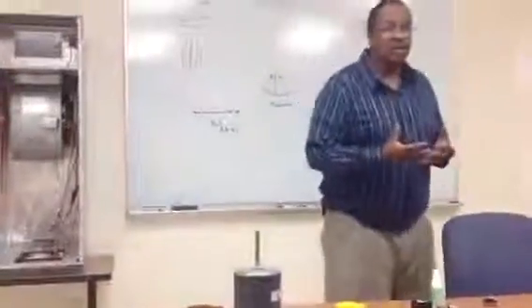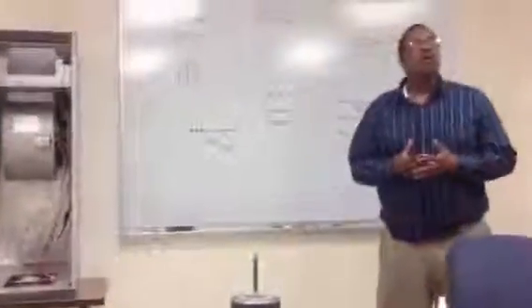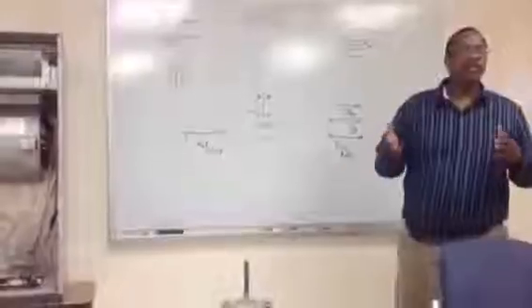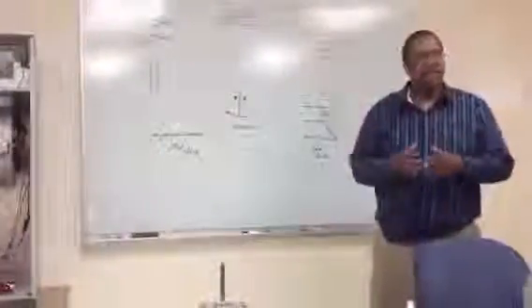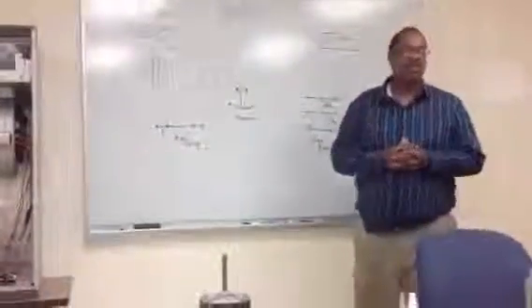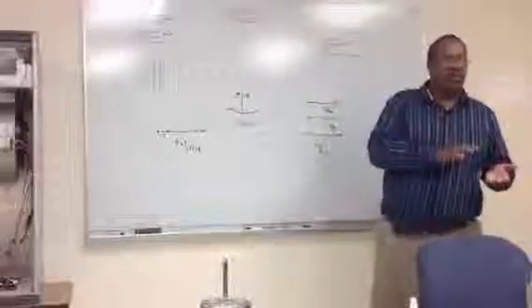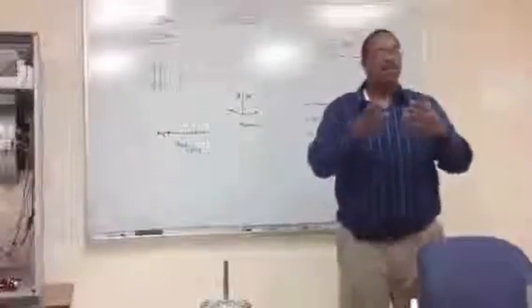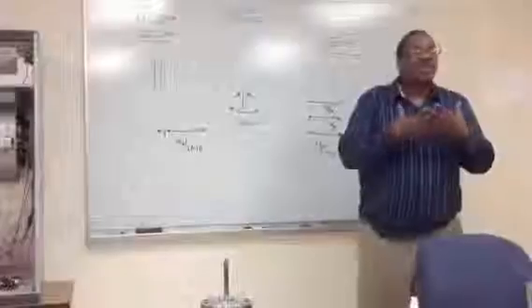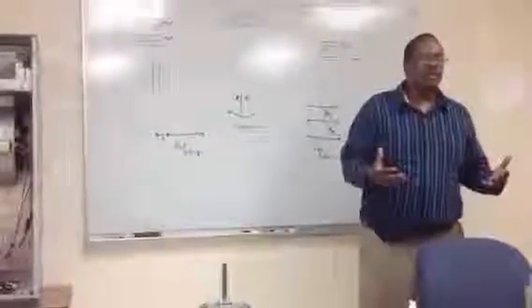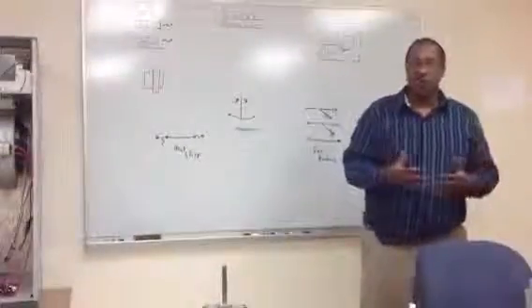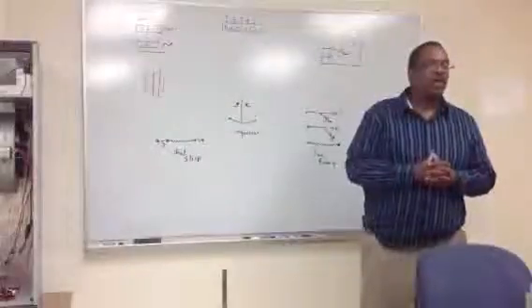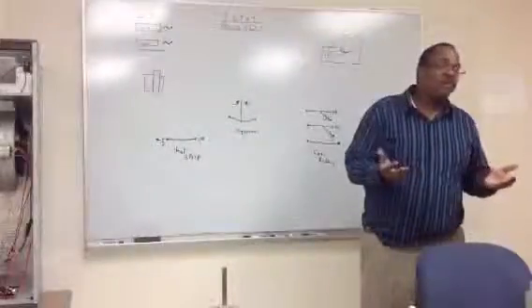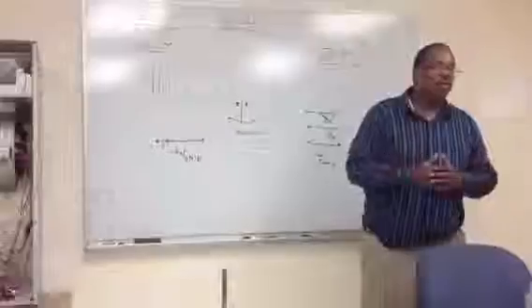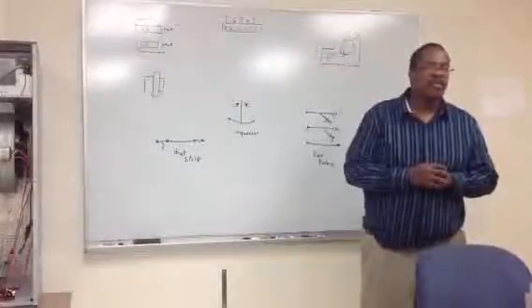Well, you have two things when it comes to wiring up a unit. You've got high voltage and you've got low voltage. Always do one or the other. Don't hopscotch, as one instructor used the terminology. Do low voltage, get it out of the way. Do high voltage, get it out of the way. Everything has a system, okay? So have a system when you go to wire up the unit. Don't just jump around, because you could leave a wire off and not know it and cause something to go wrong or waste a lot of your time.